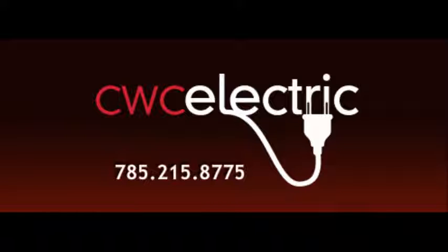And again, if you have something not working, a section of a room, you've gone and reset all the breakers, everything's on, but a section's not working. Again, you've got a connection that's gone bad, that's a possible fire hazard, and you need to have that evaluated.